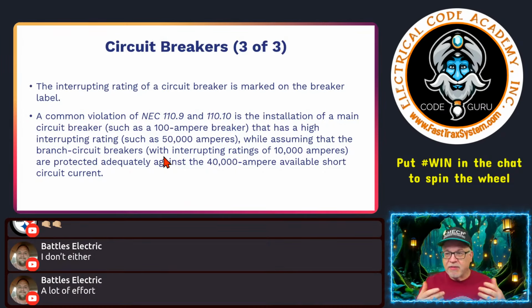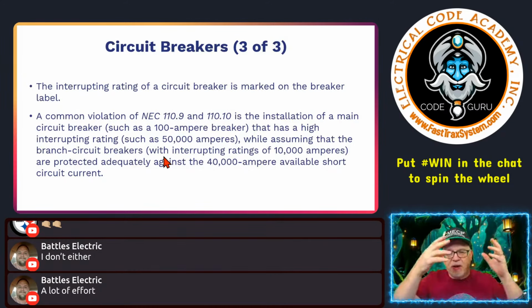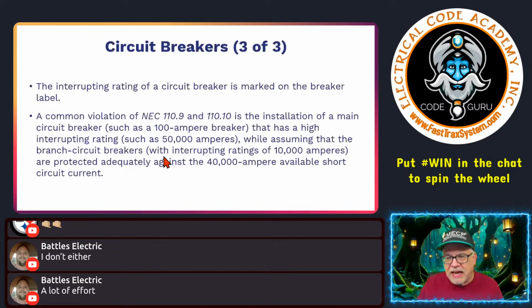right? And sometimes it's vice versa. They may have something that's higher at the end where the fault current's going to be less, and that may be fine, but up front they may have a device that is not sized properly to the available fault current. And if that's the case, that's a violation of 110.9 and 110.10 of the NEC.